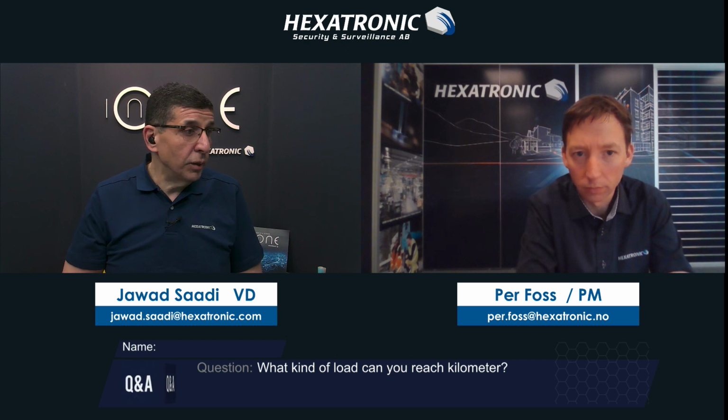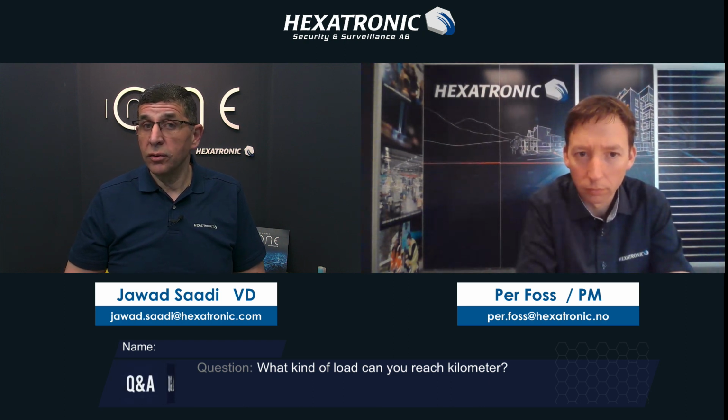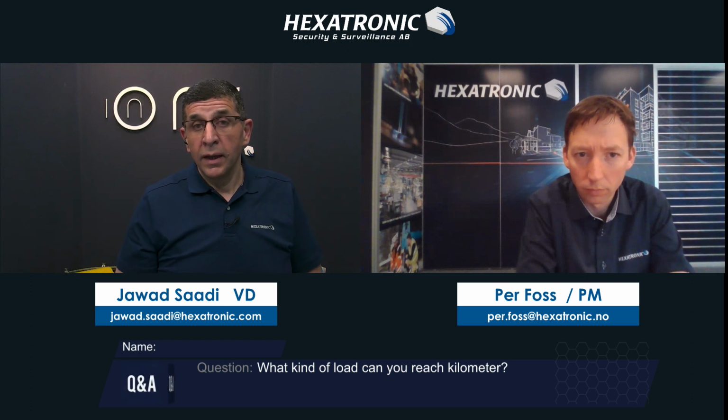What kind of load can you reach over 1 kilometer? I cannot calculate it off the top of my head, but maybe 200 to 300 watts. Don't quote me on that, but we can give you an exact estimate. I know that the maximum distance that we have for a normal camera with 18 watts is 7 kilometers. And we also have a cable that will double that distance. We can do it on the calculation tool and give you a precise answer if you tell us the exact load. But I think it is safe to say 200 watts.